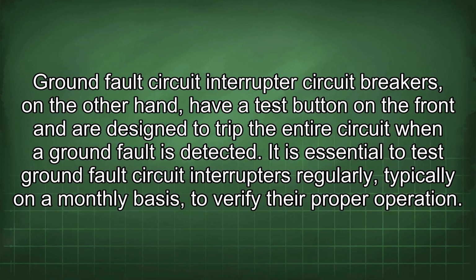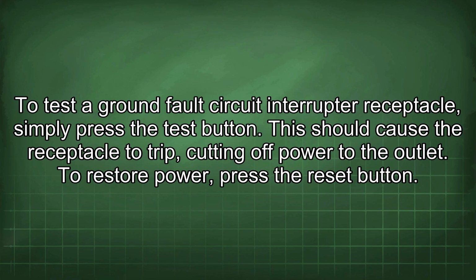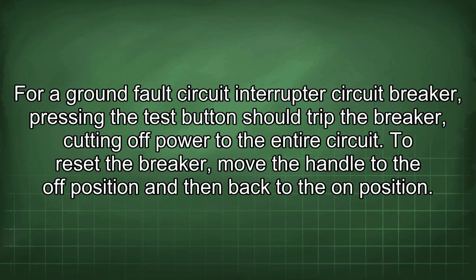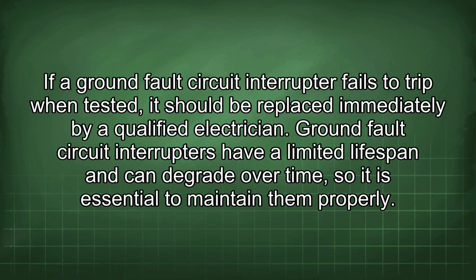It is essential to test ground fault circuit interrupters regularly, typically on a monthly basis, to verify their proper operation. To test a ground fault circuit interrupter receptacle, simply press the test button. This should cause the receptacle to trip, cutting off power to the outlet. To restore power, press the reset button. For a ground fault circuit interrupter circuit breaker, pressing the test button should trip the breaker, cutting off power to the entire circuit. To reset the breaker, move the handle to the off position and then back to the on position. If a ground fault circuit interrupter fails to trip when tested, it should be replaced immediately by a qualified electrician. Ground fault circuit interrupters have a limited lifespan and can degrade over time, so it is essential to maintain them properly.